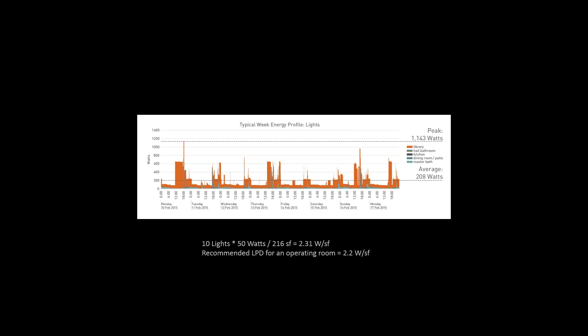Except one room, called the library, had much higher lighting than every other room. We went back and checked the lighting power density, and it came out to 2.31—for reference, that's higher than what's recommended for an operating room in a hospital. This was because the lighting installer told us they were installing one thing and installed another, and we never went out to verify, which we should have done, because it's using more energy than it should.